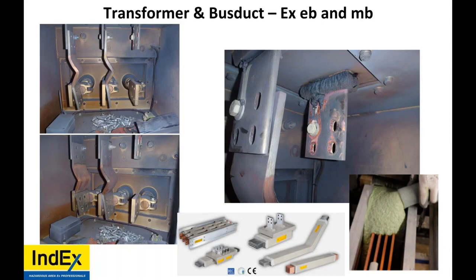It blew up because they ran it with 1 of 8 bolts on the bus link inside the transformer. So that top section that you see that is burned, that's the modular bus duct, the Ex mb bus duct. So when you do things incorrectly, you would think that you could just replace the bus links. You cannot. That Ex mb bus duct, remember, is concrete. So the entire section, whether it be 30 meters or 1 kilometer, you're looking at replacing it all. So millions of dollars, perhaps.